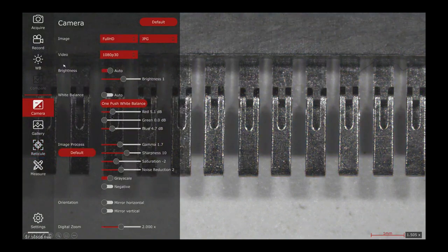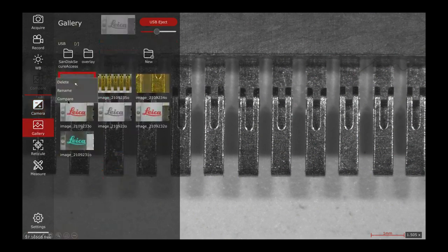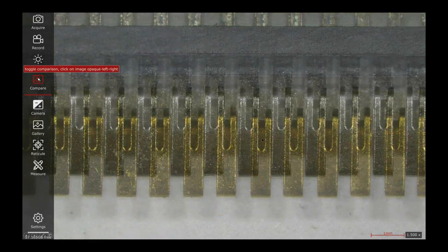Now we come to the compare function. The compare function allows me to check here in the gallery an image that I want to compare my live sample under the microscope with. So if you want to toggle between the comparisons, you have here the image, how it looks when you have an overlay. And as I said before, I'm using the grayscale image so that you better see the difference between the comparison image and the live image.